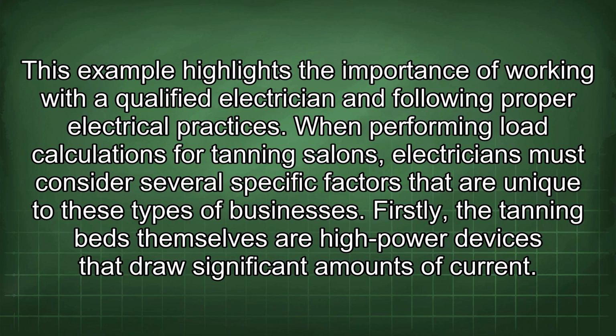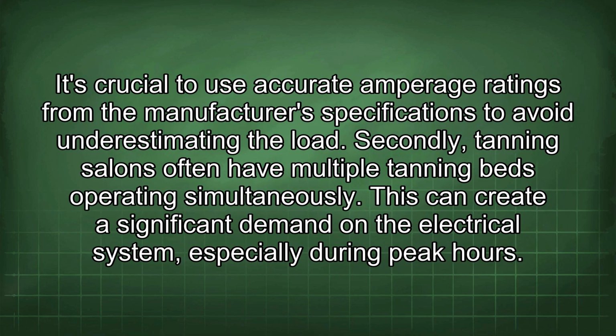When performing load calculations for tanning salons, electricians must consider several specific factors that are unique to these types of businesses. Firstly, the tanning beds themselves are high-power devices that draw significant amounts of current. It's crucial to use accurate amperage ratings from the manufacturer's specifications to avoid underestimating the load. Secondly, tanning salons often have multiple tanning beds operating simultaneously. This can create a significant demand on the electrical system, especially during peak hours.